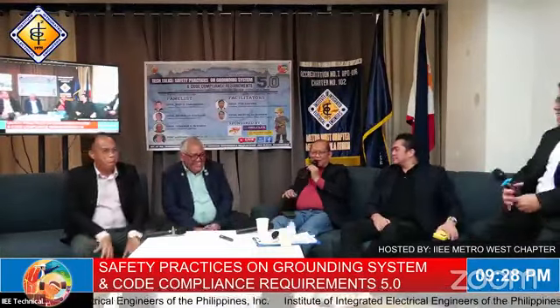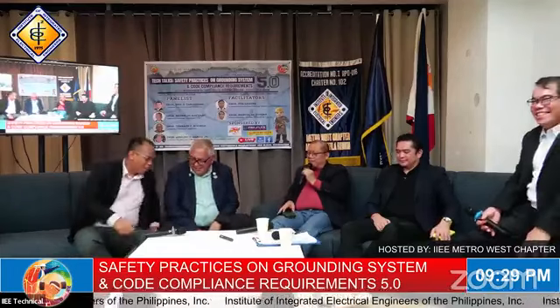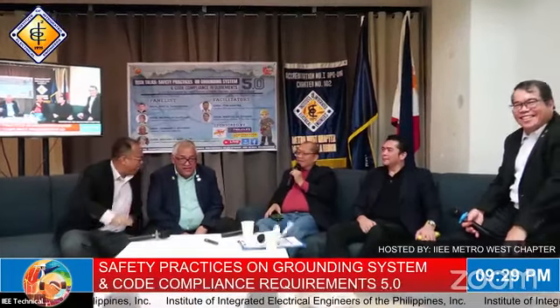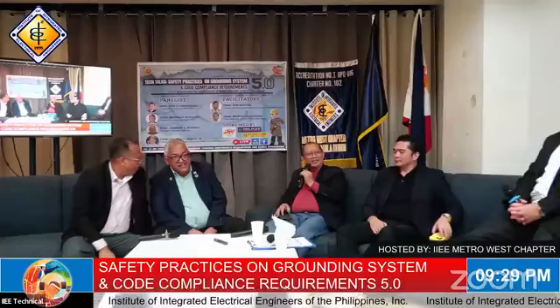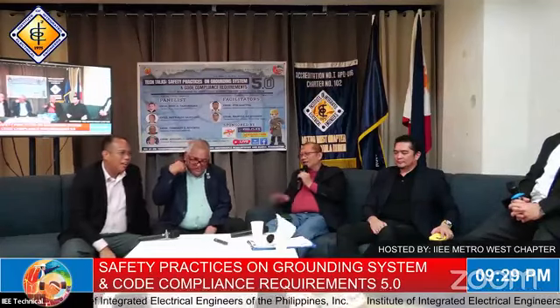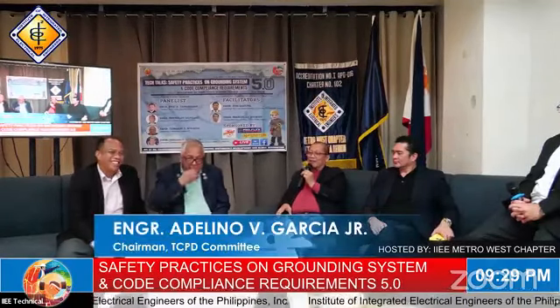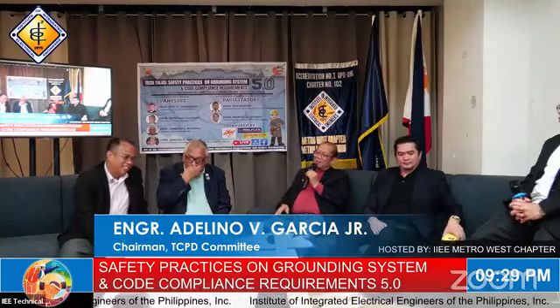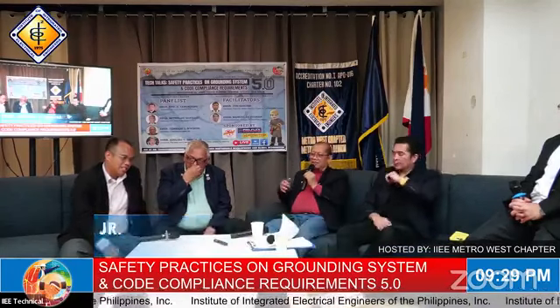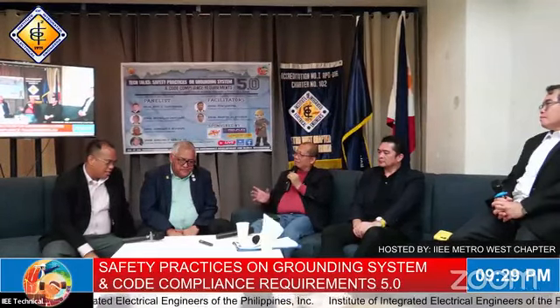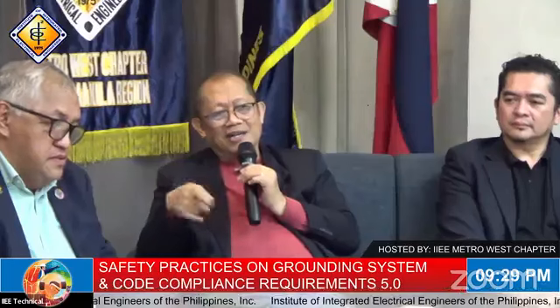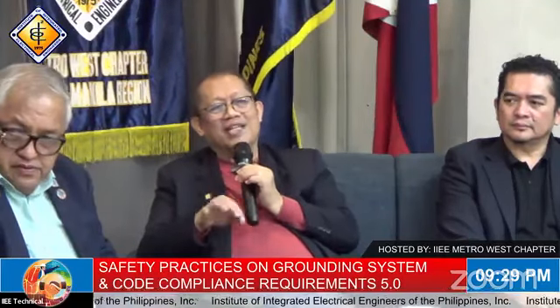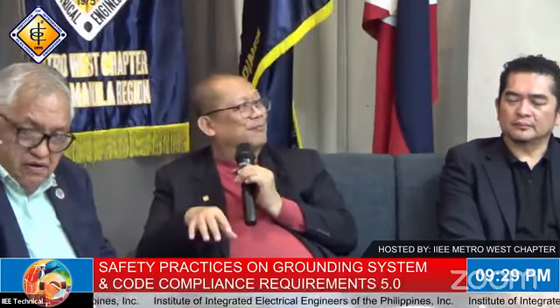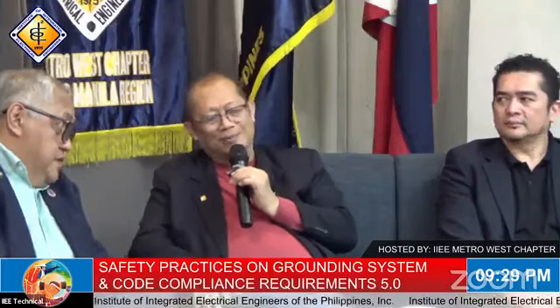I'm not sure about the formula defined by IEEE 80, but it's there. It's not dependent on the voltage level, it's dependent on the available fault current of the system. So maybe it's not 69 kV, but your fault current is X — all of that will redound to the fault current. When you calculate mesh and step potentials or touch potentials, it's directly proportional to the available fault current in the system, not the voltage.